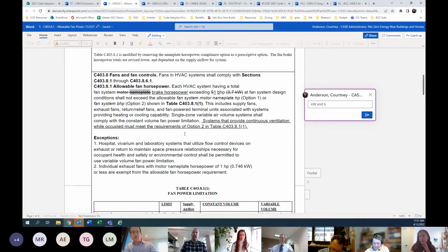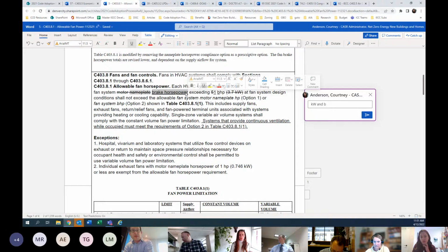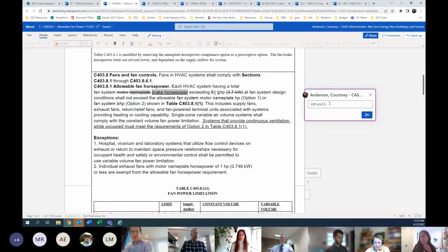Is that brake horsepower I underlined new to the code? It should not be new, but it may be new here in this language. It should be defined somewhere. Brake horsepower would depend on the design, whereas nameplate would be the actual fan motor selected. In your amendment language it should have been underlined because it's new for this bit of code, correct? Yes, I believe so. The base code language is motor nameplate horsepower; brake is the added term.